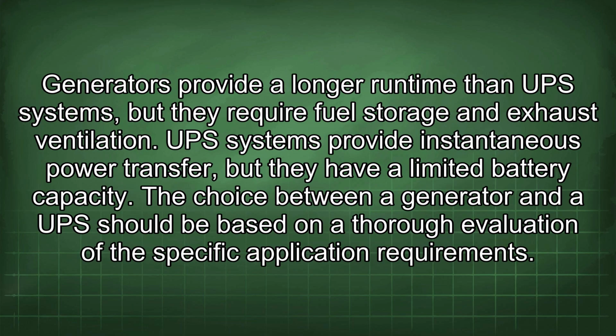Generators provide a longer runtime than UPS systems, but they require fuel storage and exhaust ventilation. UPS systems provide instantaneous power transfer, but they have a limited battery capacity. The choice between a generator and a UPS should be based on a thorough evaluation of the specific application requirements.